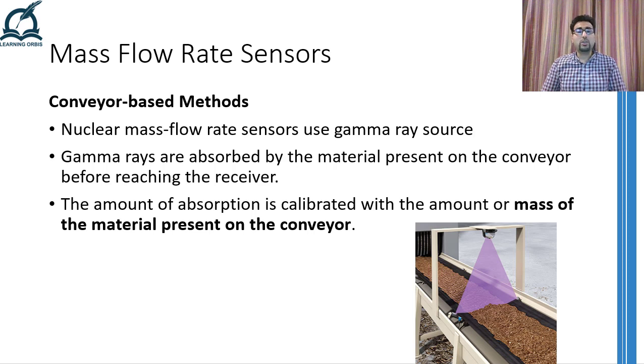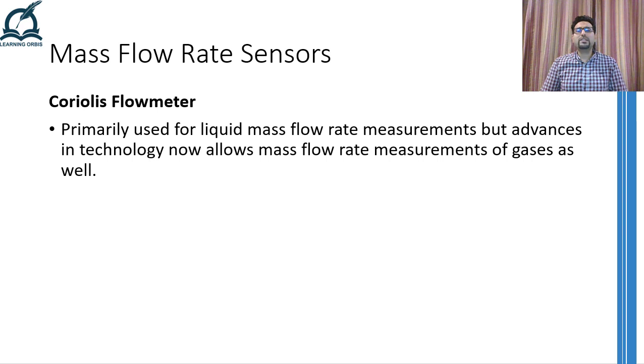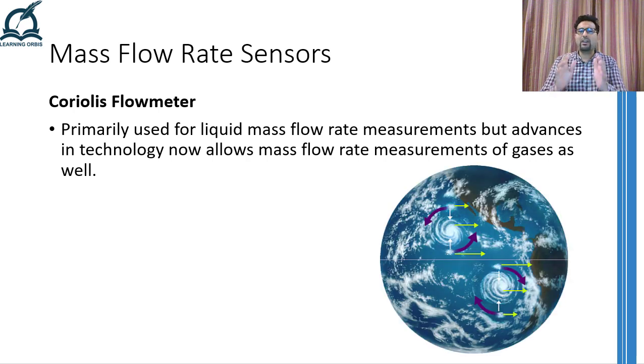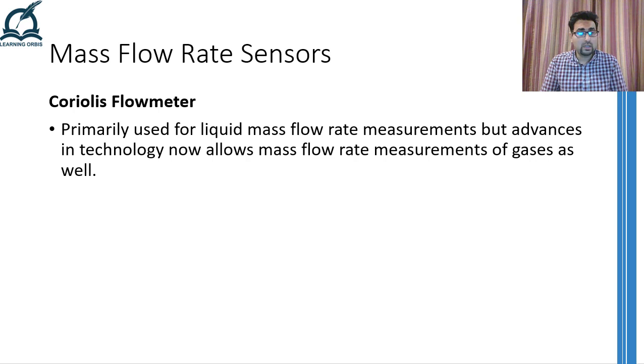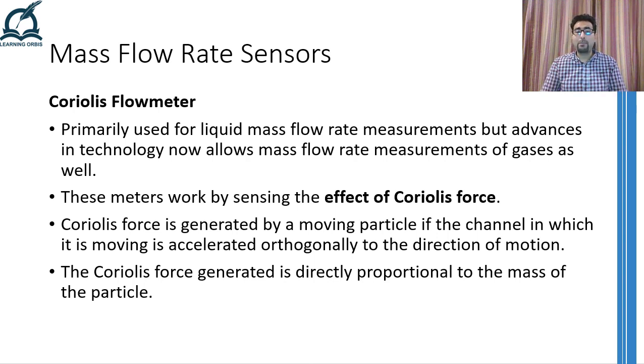The next mass flow rate sensor is called Coriolis flow meter, and it is quite widely used mass flow rate sensor for mass flow rate measurements of liquids. However, the advanced versions of it can be used for gases as well. The main working principle of this sensor is based on generation of Coriolis force and measuring its effect. You might have heard the word Coriolis in relation to meteorology or some similar situation because Coriolis force is responsible for the cyclones and the movement pattern of clouds all around our Earth. However, sticking to our topic, Coriolis force is generated when a particle moving in a particular direction is accelerated orthogonally to the direction of motion. This force is responsible for making the particle go in a cyclone-like motion. The Coriolis force which the particle experiences is directly proportional to the mass of the particle.